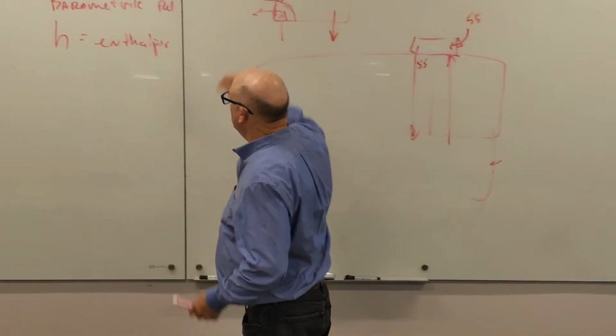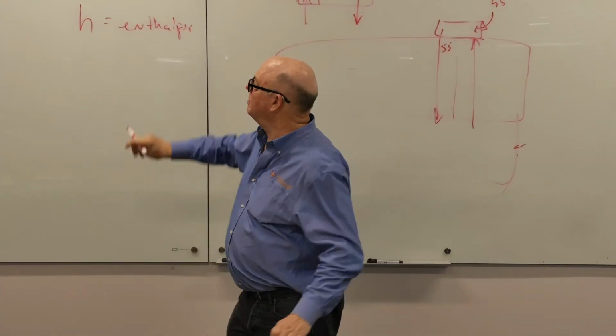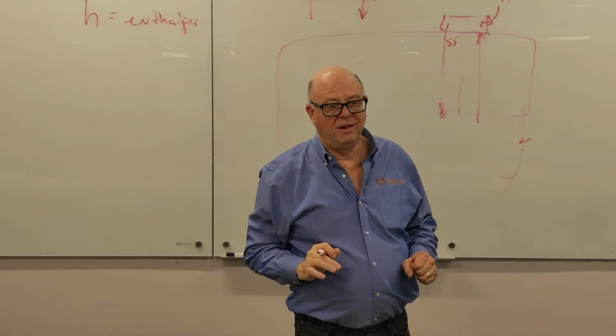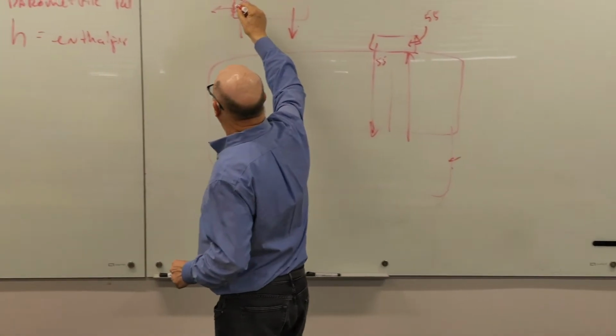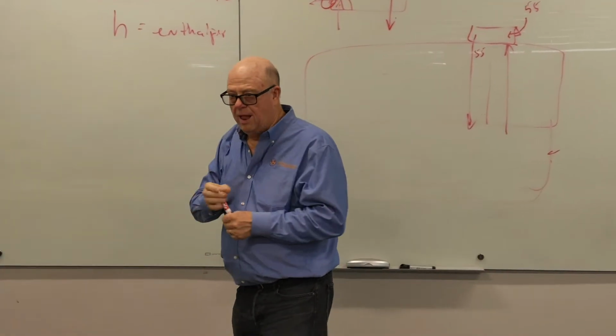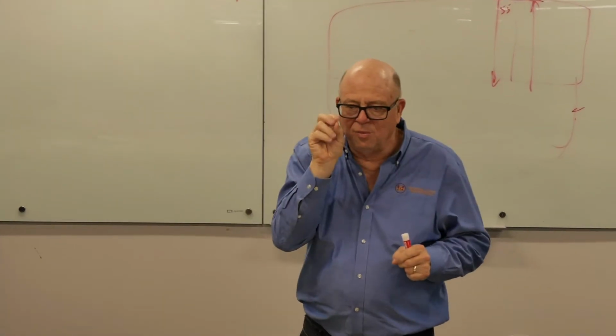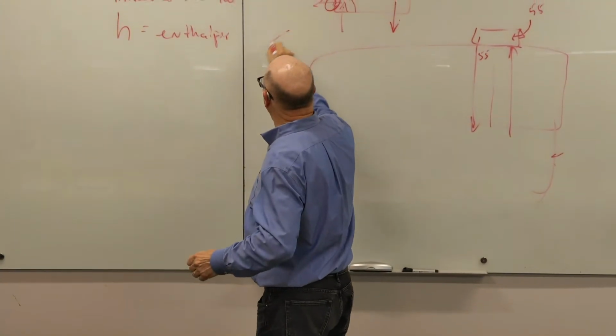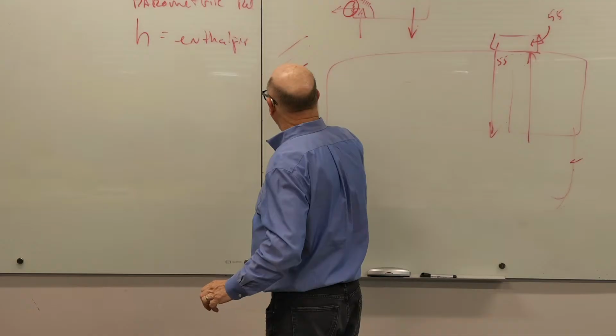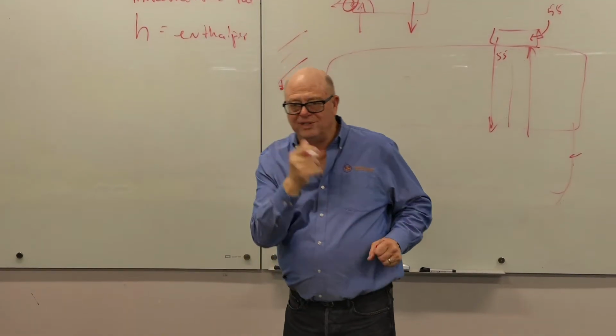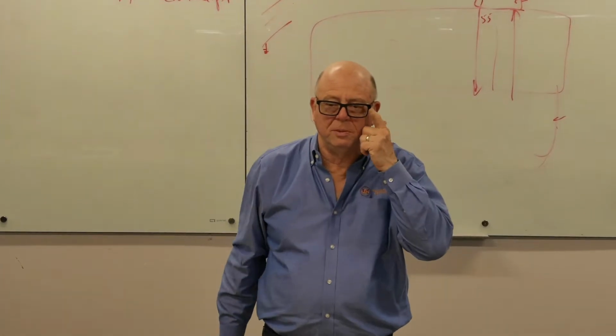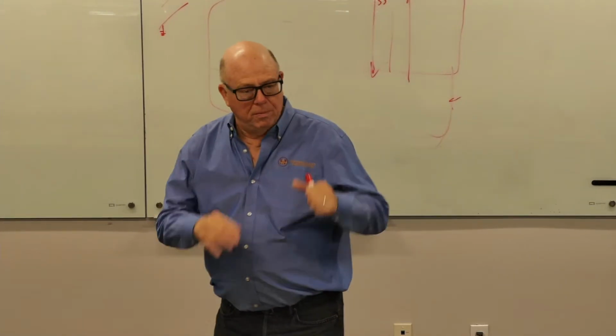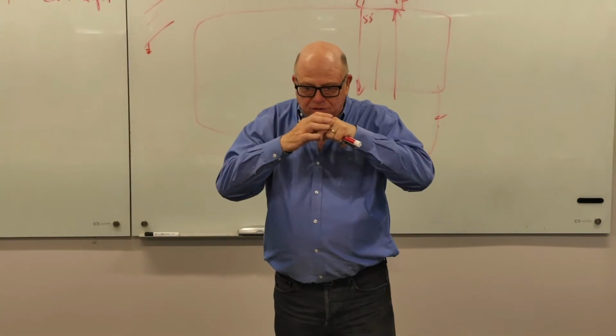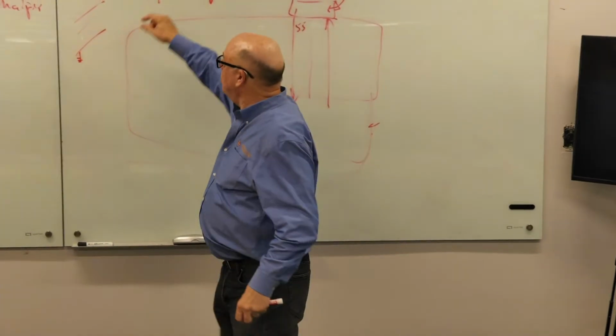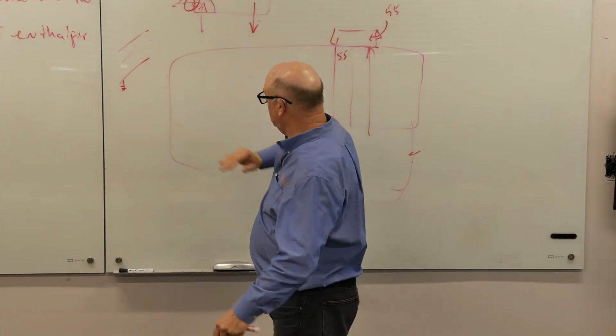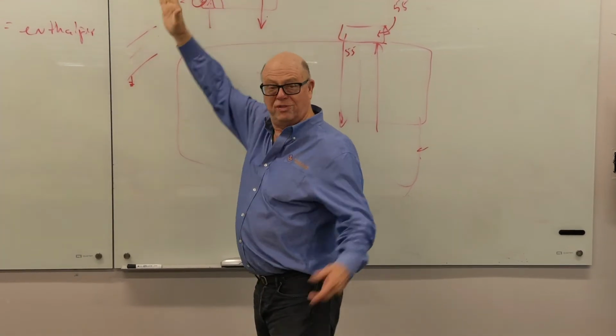Okay. So the barometric relief had to do with that damper. And all a barometric relief does is, it's got a little weight. One example of a barometric damper setup might have a little hangy thing with some weights that you screw on. That's a really simple, cheap one. There are better ones. But remember, we're blowing up the first floor with the economizer air, right? So you could come up with an equivalent pressure that you didn't want to get above, and that would trigger the thing to open.